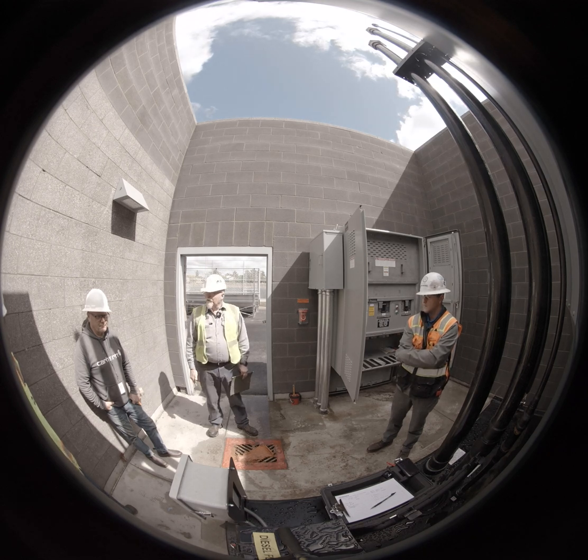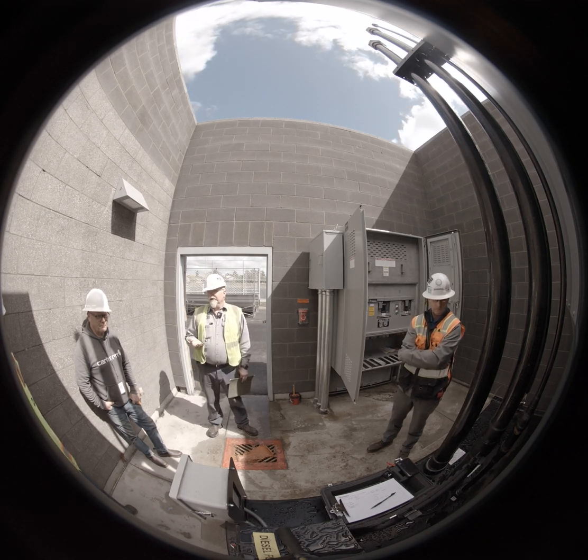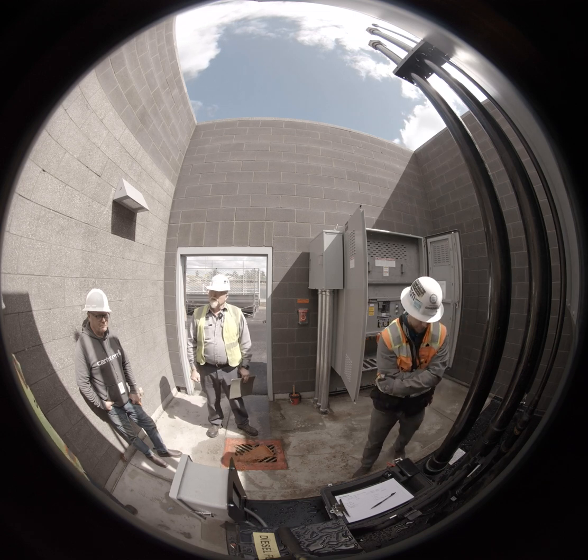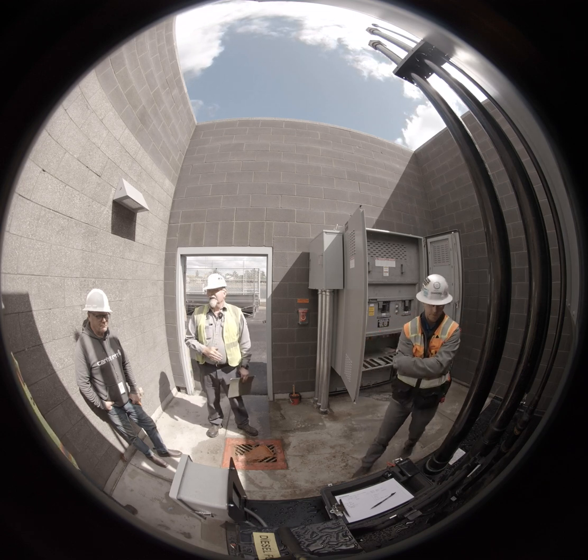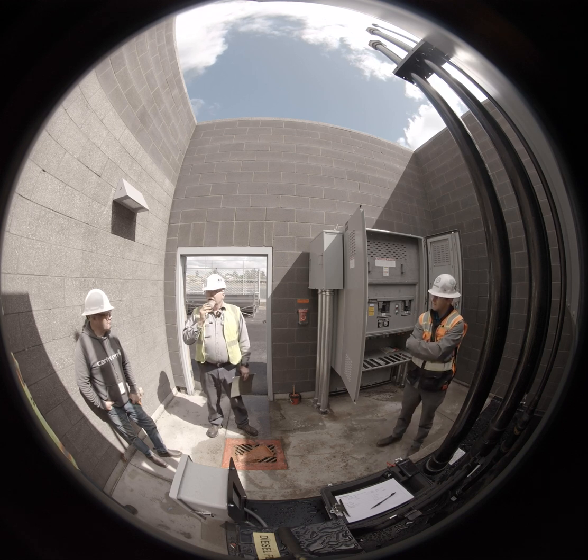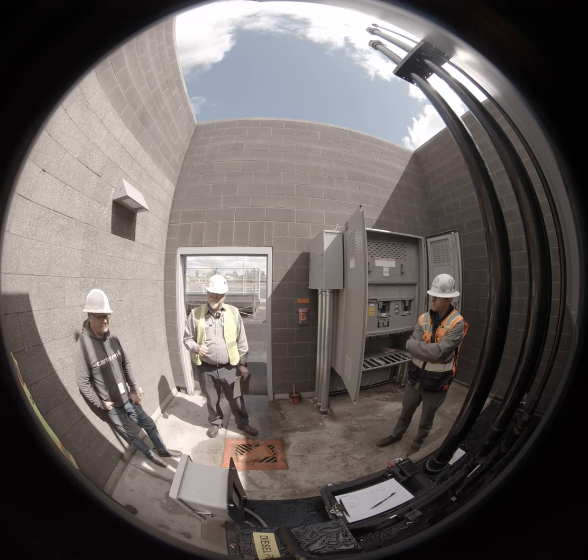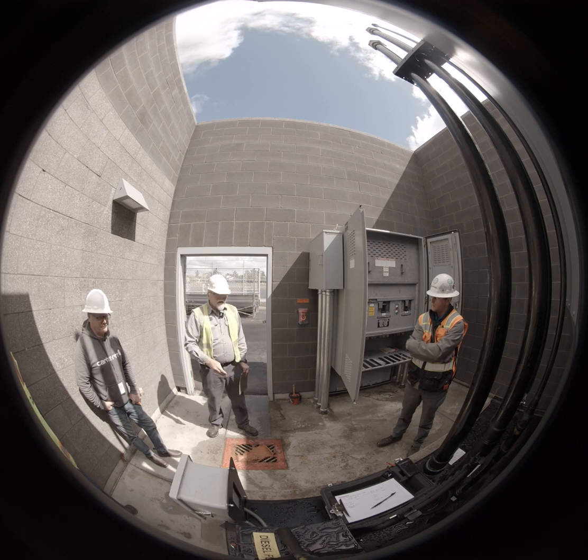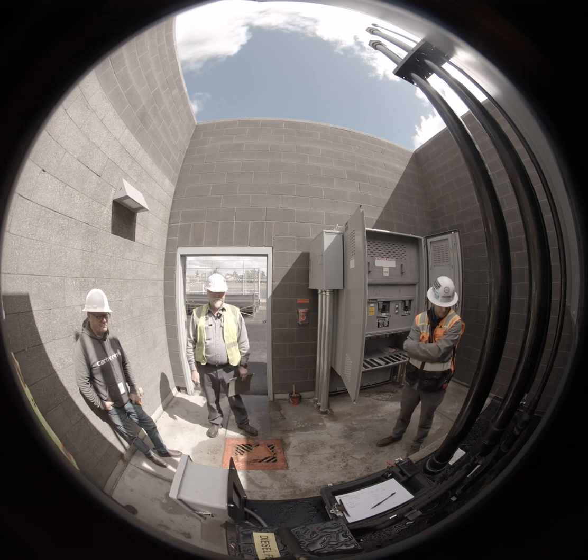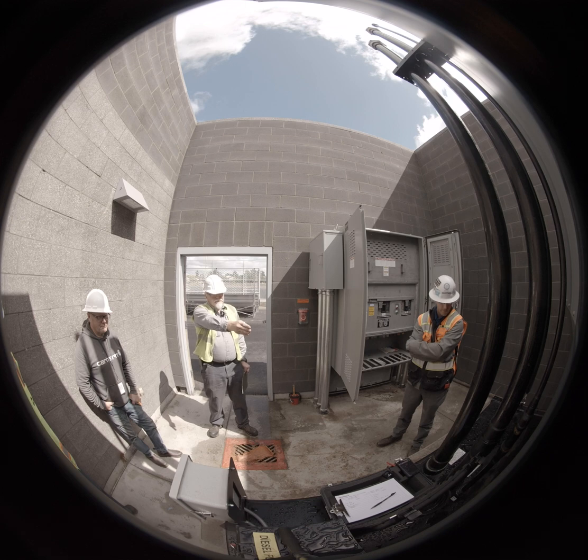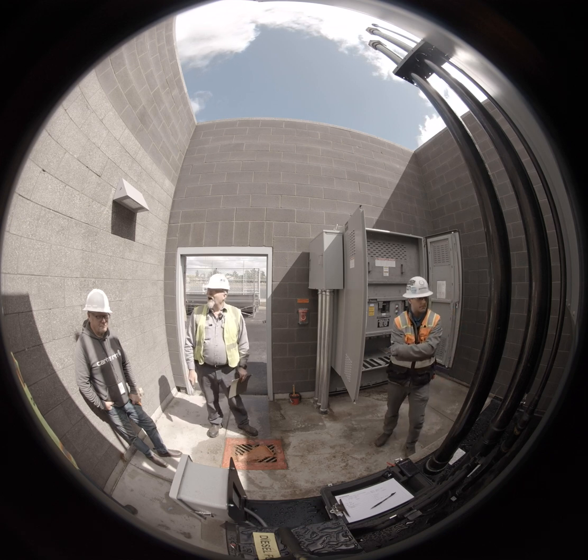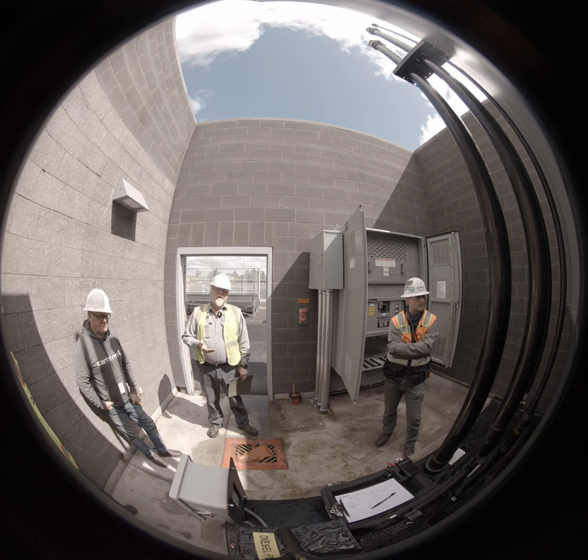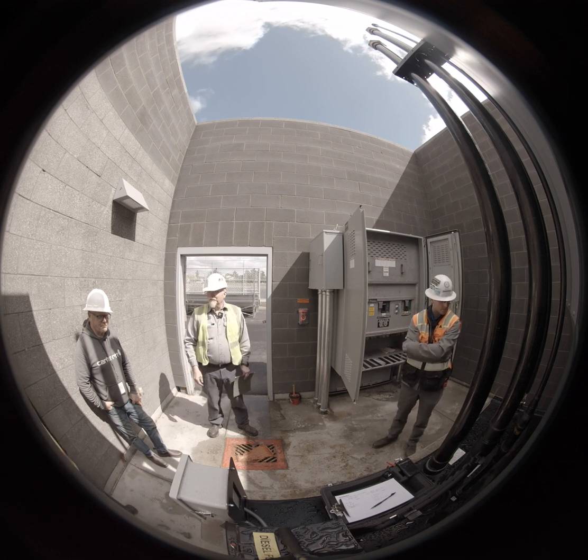The next pipe forward is what they call an explosion vent. The explosion vent is set up so that if, for some reason, the fuel ignited, it would allow the pressure inside the tank to dissipate by lifting the cap off way up in the top up here and relieving the pressure. The front one, again, is another explosion vent, but that is for the annular space on the front of the tank. The funny piping setups over here on the front are designed for, in the event of an earthquake, the fuel will not slosh and shoot back up the pipes.